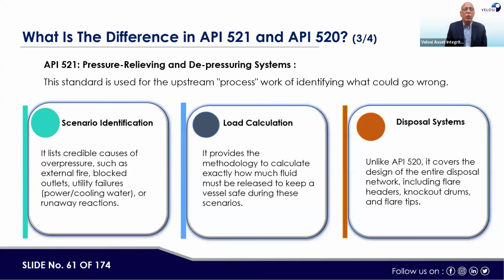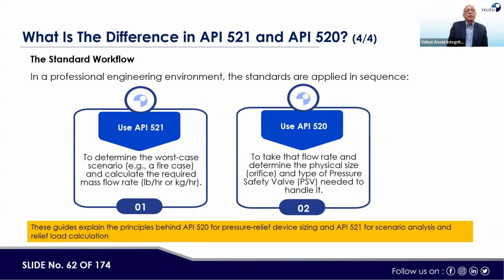Scenario identification means whether the outlet is blocked, whether there could be a fire, there could be cooling water failure, there could be utility failure, and so on. Whereas load calculation means how much volume of fluid would be coming out, and then how this fluid would be handled by a relief system, what should be the type of the relief system, the header sizing, the knockout drum sizing, and flare sizing itself also. Then API 521 determines the worst case, and to take that flow rate and determine the physical size, like orifice and type of pressure safety valve, is covered under the API 520 standard. These guides explain the principle behind 520 for pressure relief device sizing, and API 521 for scenario analysis and relief load calculations.